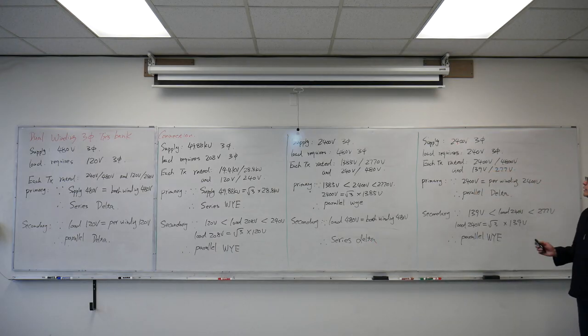Last example: 2400 volt supply, 240 volt load requirement. Transformer 2400, 4800, low voltage side 139, 277. Primary side, 2400 volts equals this 2400 volts, so I know it's going to be delta, equal to the per winding voltage. So I know it's parallel delta. Secondary side, 240 is not equal to 139 and not equal to 277, so it's not going to be delta. But 240 is larger than 139 and smaller than 277. So I check 139 times root 3 equals 240. So I know the secondary is going to be connected parallel Y.